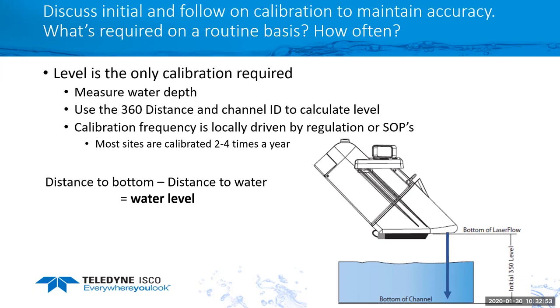Now, as far as the calibration frequency, it's really site specific, and a lot of it is driven by local regulations on how often you have to do that, or just your standard operating procedures. Now, with that said, just talking to people all over the country, a lot of times they'll go out 2 to 4 times a year to do level calibrations. So they go out and check the application, calibrate or verify that the level is still reading properly.